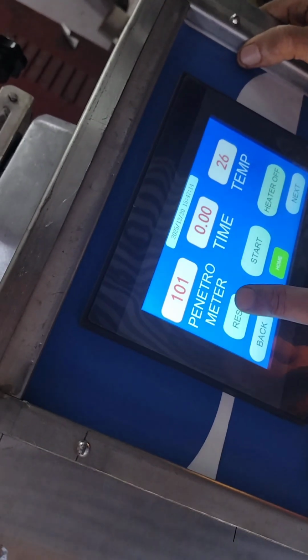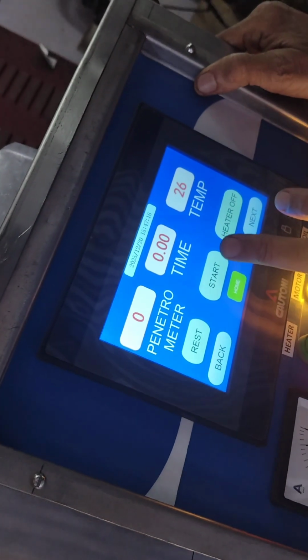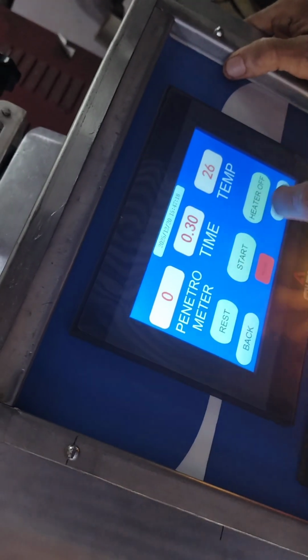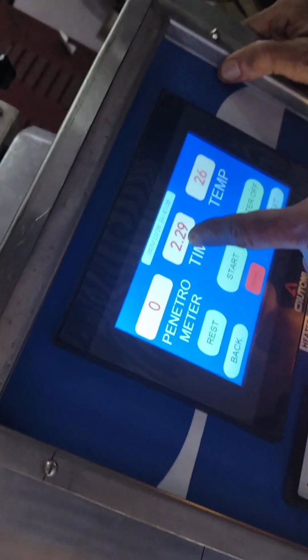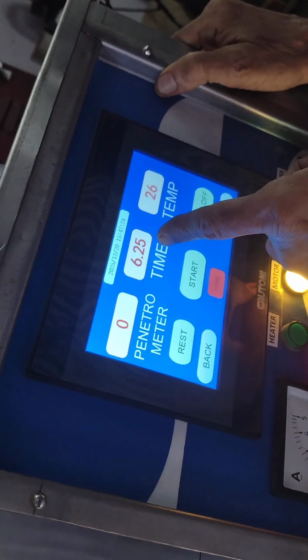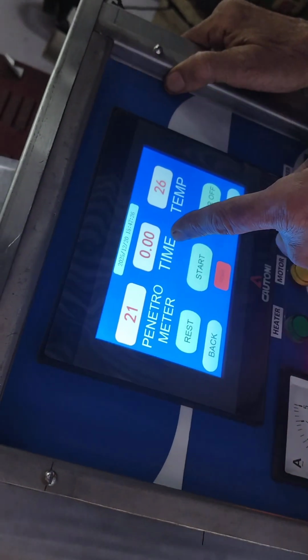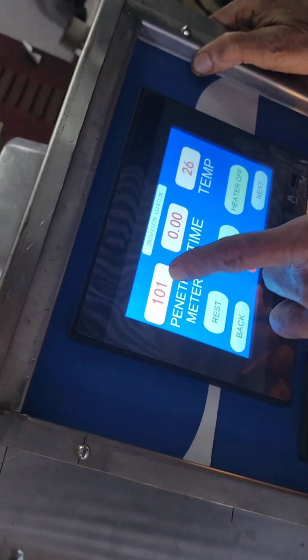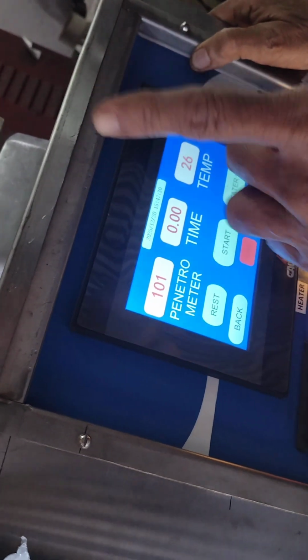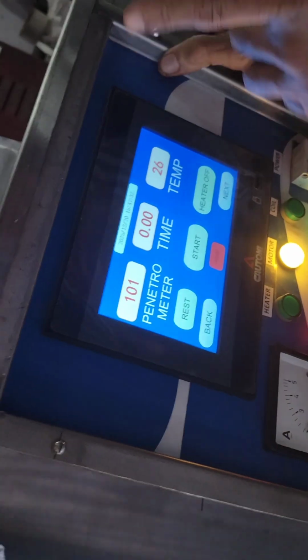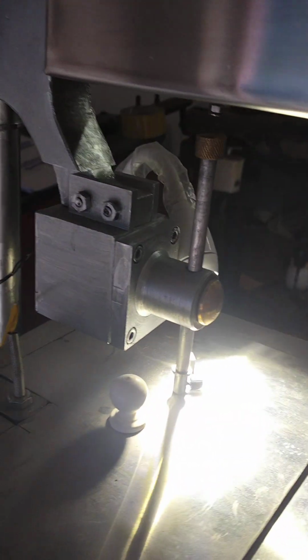Reset, I am going to do the reset. The start timing is there, see the 5-second down counting is there. That is 0, it has come to 101, meaning again the same reading is there. Whatever the calibration block height is, it is showing that. That means the calibration of this instrument is correct.